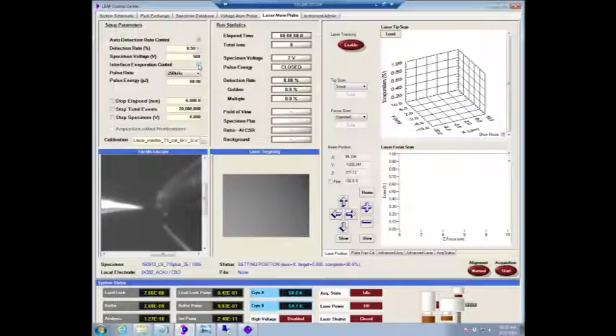The reason this was implemented is that if you have a multi-layer stack, you might have a low evaporation field layer, a high evaporation field layer, and then you go to a low evaporation field layer again. As soon as you go out of the high evaporation field layer, the low evaporation field layer will just start to evaporate like crazy, and it will usually end your measurement because your sample will blow up. The interface evaporation control detects that and steps down the voltage fairly rapidly. This is not particularly helpful if you've got anything but that case. So usually for most samples, unless you've got a good reason, keep it switched off.